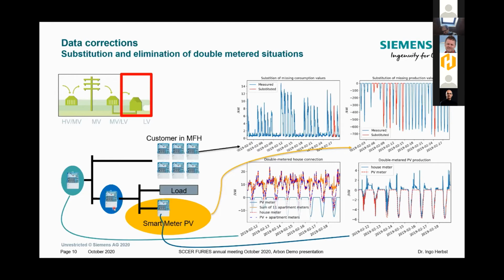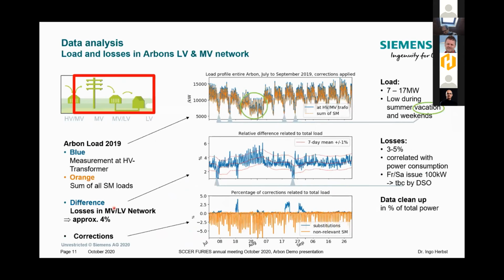With all those corrections, we come to the results I'll show now. This is taking 10,000 smart meters and comparing to the high voltage transformer power measured at one spot. If you subtract one from the other, what comes out in the middle plot is the losses you see—here it's 3 months of data, showing typical losses around 4%, a bit higher when the load is lower, like during summer vacation time.